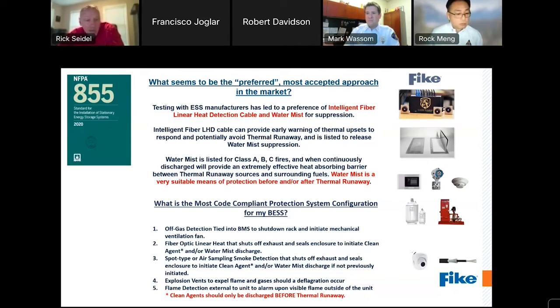Whereas the most code compliant protection system, if you followed NFPA 855 to the letter, you would probably have several combinations and several types of systems installed that may overstep one another and make it much more complicated than it may need to be. But there are ways you can get to a very effective protection system by going through some of the practices that my previous colleagues have mentioned as well from a hazard analysis standpoint. Next, please.